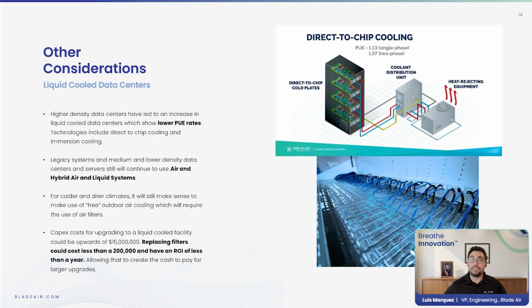The reality is, however, that there are still legacy systems, and medium and lower density data centers will continue to use air and hybrid air liquid cooling. I just saw yesterday a post on LinkedIn about a Vertiv hybrid modular configuration, which they're pushing for new and existing data center builds, in which they use both the air and liquid cooling in their systems, because not all racks need that liquid cooling. Also, I am coming to you from Toronto, Canada, and for colder, drier climates like ours, it will still make sense to continue to use that free outside air to help cool and maximize heat exchange. And obviously, anytime you're bringing in outside air, it will require the use of filters.